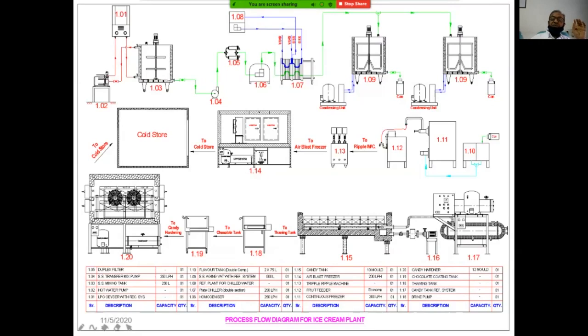It will go to the continuous ice cream freezer. We'll discuss this again in the next slide. The function of this one is to convert the liquid into partially frozen ice cream. So again, the second refrigeration requirement is in the plate chiller, then the aging vat, and then the continuous ice cream freezer for freezing the ice cream. This is a unit where we require refrigeration to take the liquid from plus 4 degrees centigrade to freeze partially, not completely, to around -5 to -6 degrees centigrade, and make the ice cream.